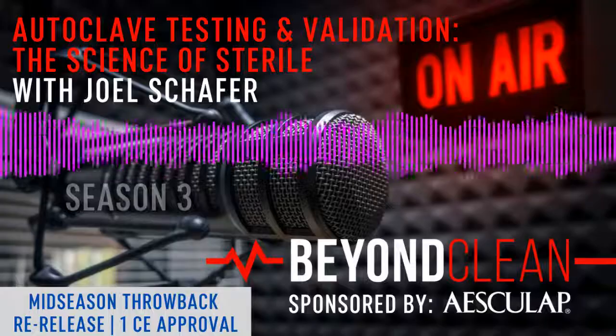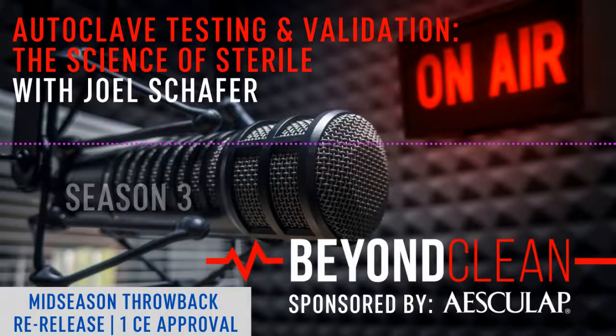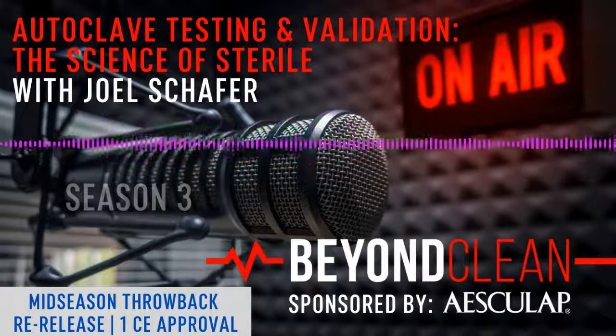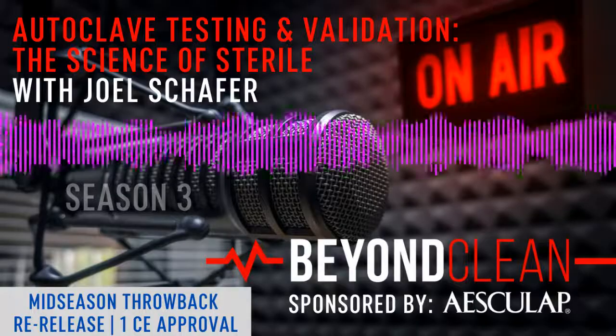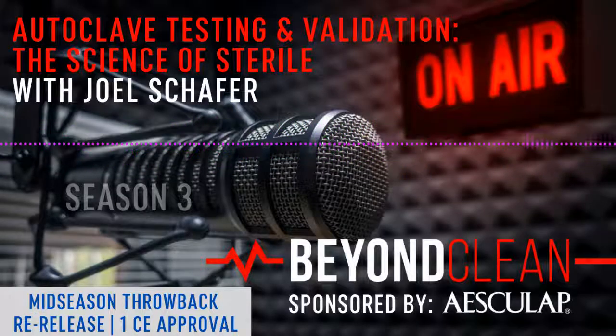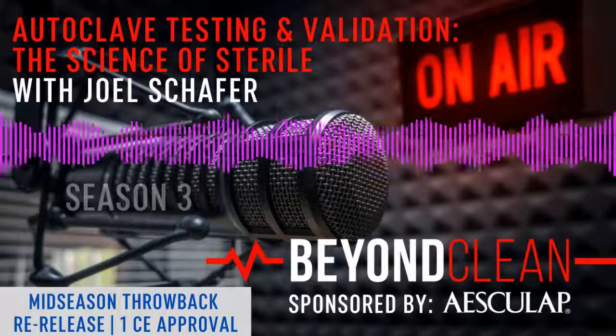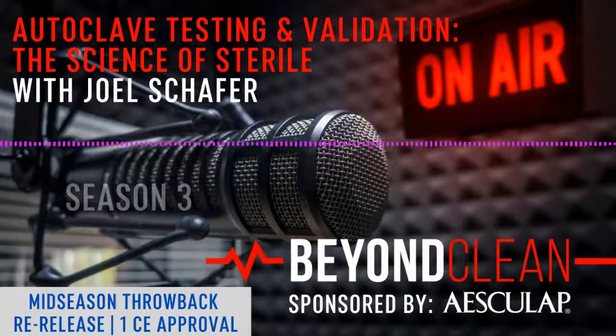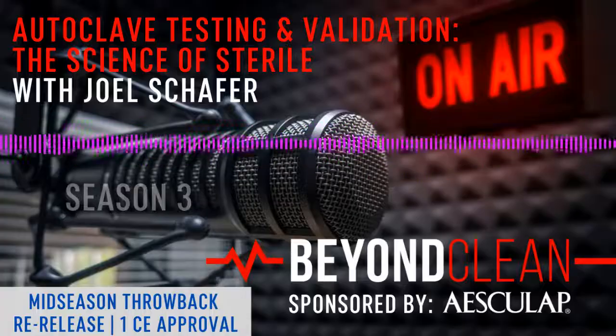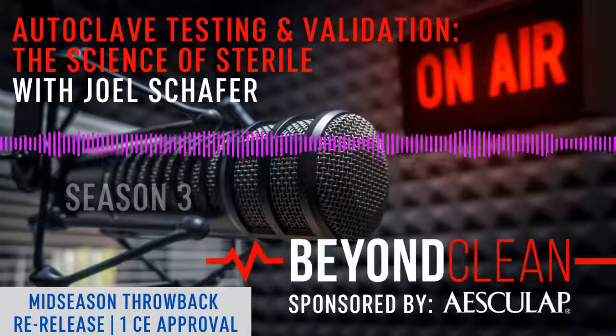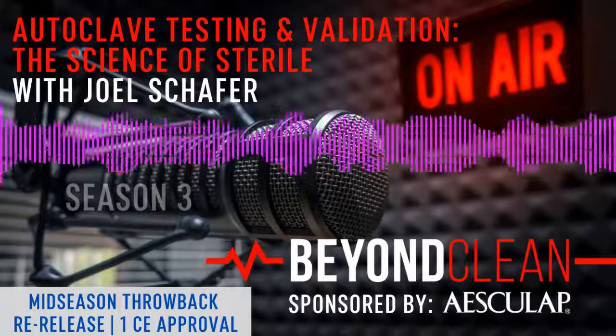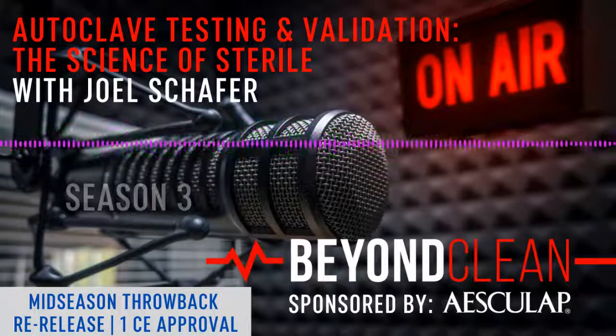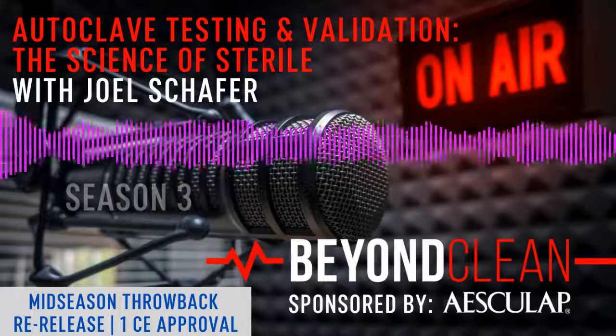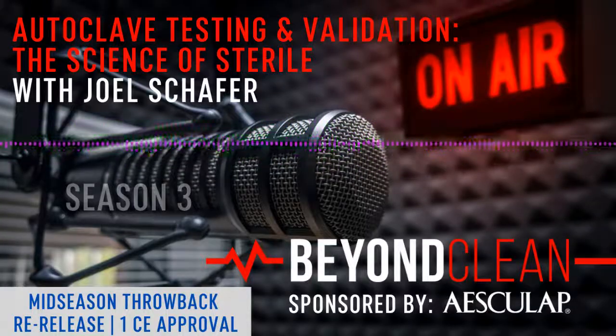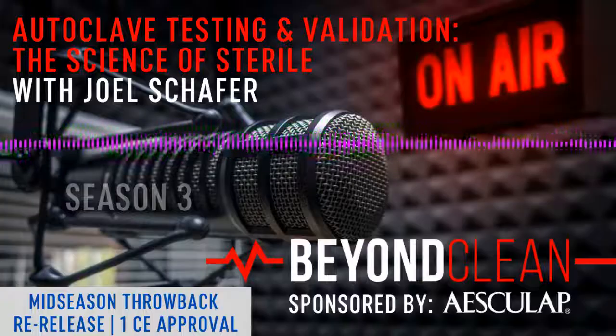I believe biologicals are a great tool for daily verification of lethality. But once again, I don't believe that they prove that you're reaching the parameters set aside by AAMI for sterilization. I'm not going to get into an argument with the big biological manufacturers. I'm not ready to take on that battle. I think they have their place, but I think verification is a high level test that leaves nothing to be deciphered. The data is the data, and the data doesn't lie. And so if all the parameters are met, then there's no reason for it to not be an effective sterilization cycle. We've all heard of biologicals that tested that the lethality was reached, and we know that the load aborted in the middle of the exposure phase. I haven't personally witnessed that, but I have heard stories similar to that from various people.